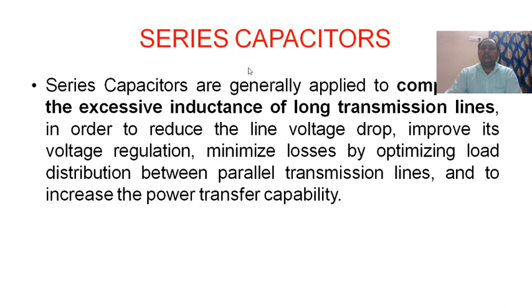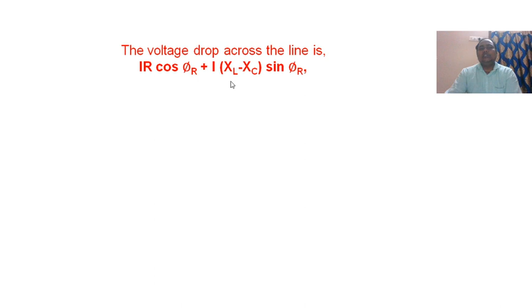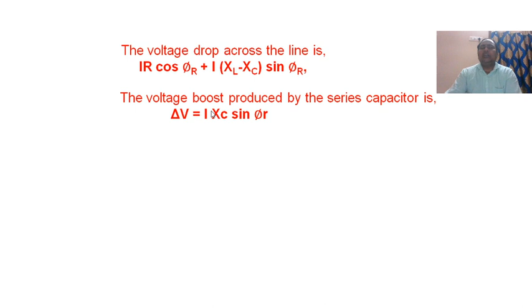This is the formula for voltage drop: I R cos phi r plus I of (XL minus XC) sin phi r. So we must decrease the net reactance in a component. If you decrease the net reactance, automatically the power factor in a system improves. The voltage boost produced by the series capacitor is the change in voltage, I XC sin phi r. If you increase the capacitive reactance, automatically the net inductive reactance decreases.